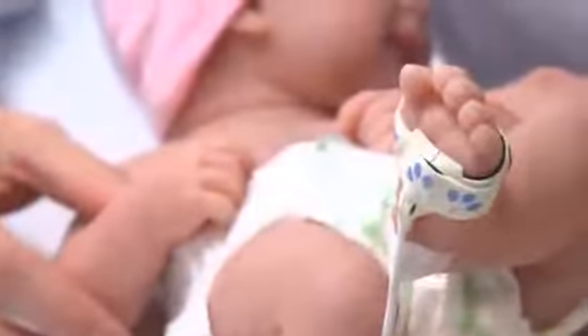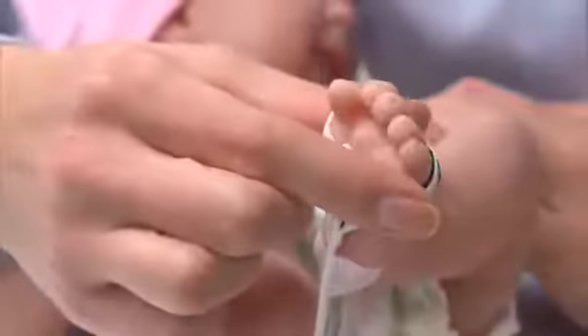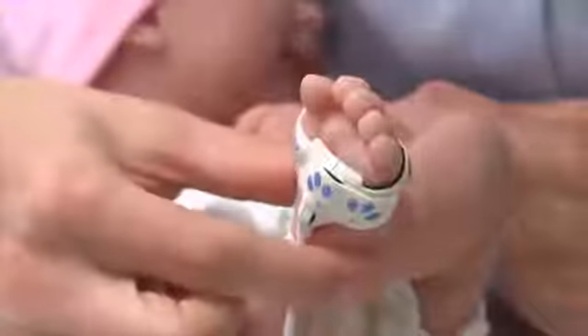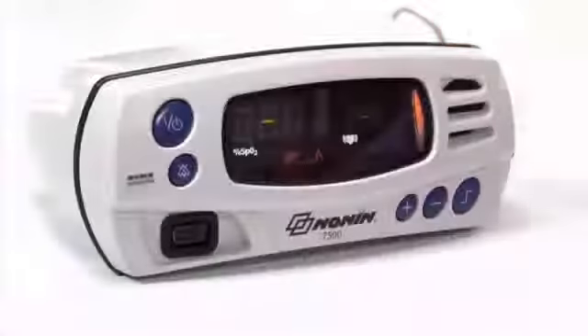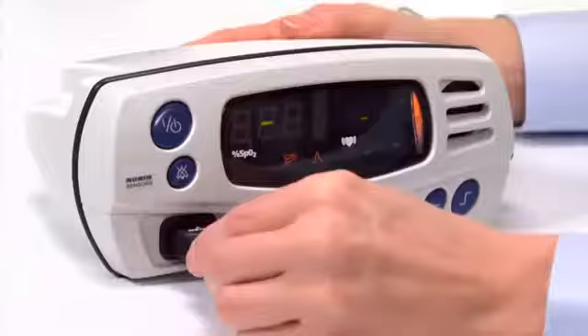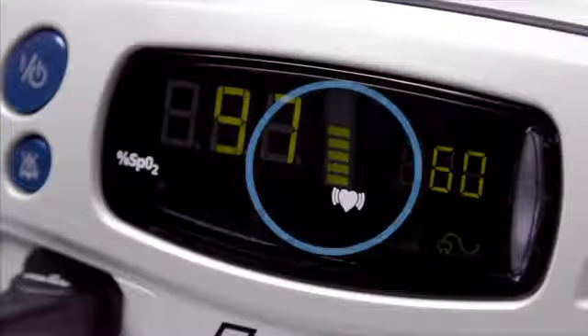For both infants and neonates, don't wrap the sensors or tape too snugly. Tight wrapping can restrict blood flow and affect sensor accuracy. You're ready to plug the sensor into the Nonin pulse oximeter to measure oxygen saturation and pulse rate.